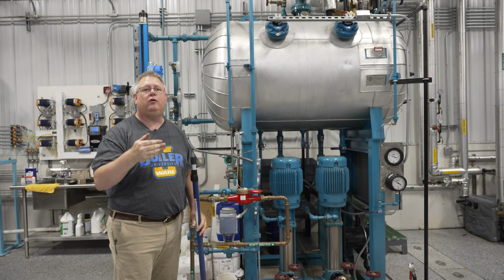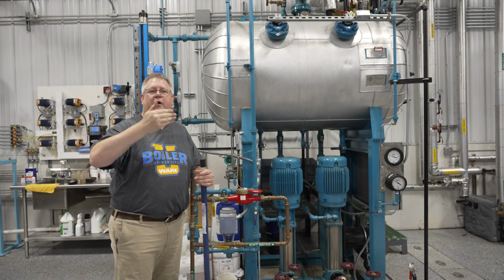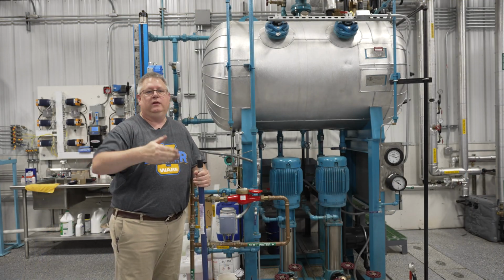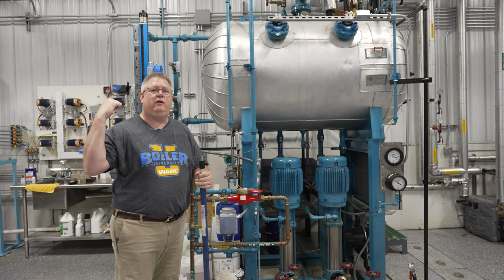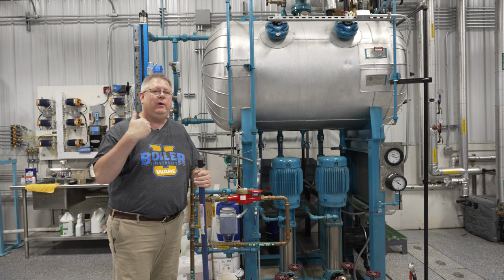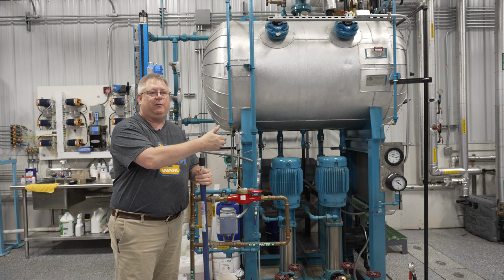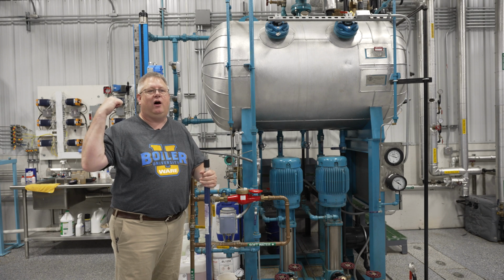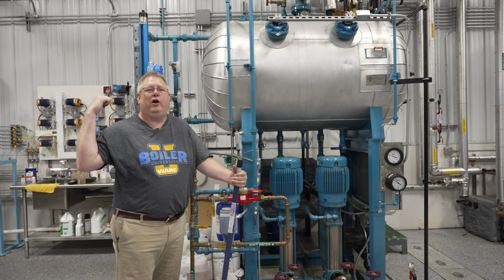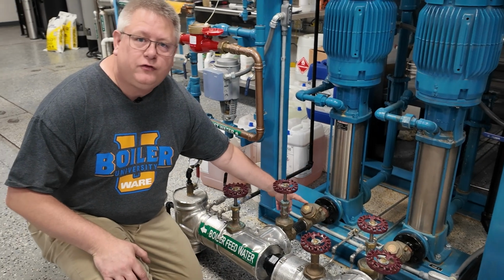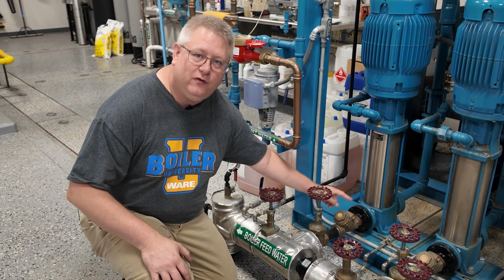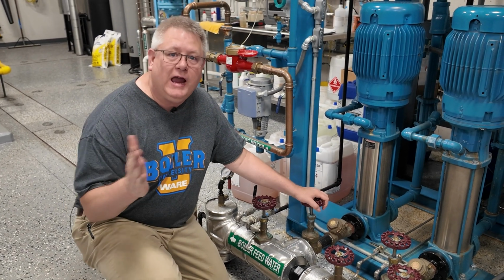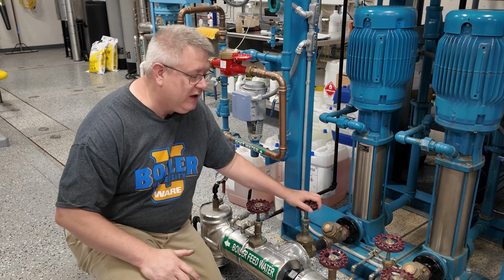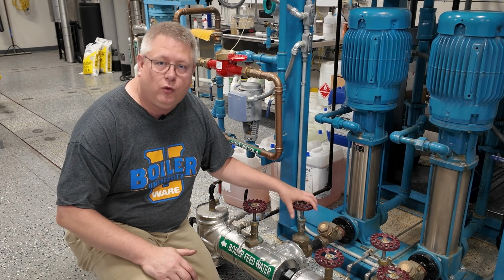And that's critical because if we go over pressure on the deaerator or we lose pressure on our feed water softener, the last thing we want to do is put steam from the deaerator back in the softener. It'd be a goner. We've also got check valves on the outlet of each pump. That way we can rotate pumps without manually having to isolate each individual pump.